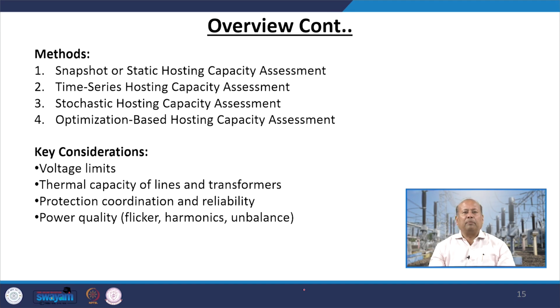Methods. There are four different methods to calculate the hosting capacity. One is snapshot or static hosting capacity assessment. The second is known as time series hosting capacity assessment. The third is stochastic hosting capacity assessment. And the fourth is optimization based hosting capacity assessment. What are the constraints we are considering? Voltage limit, thermal capacity of lines and transformers, protection coordination and reliability, and power quality. We will see during the next 10 to 15 minutes how those hosting capacity assessments can help the distribution system to be free from thermal capacity violation, voltage limit violation, protection coordination violation, and power quality violation.